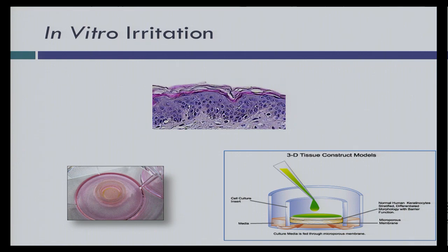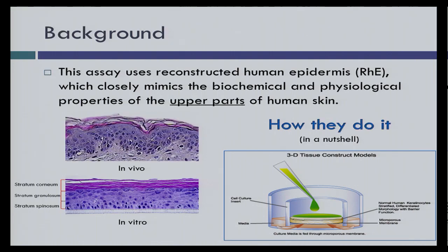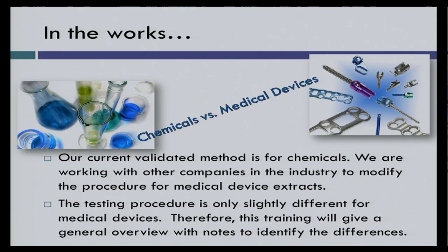The in vitro irritation alternative uses reconstructed human epidermis (RhE) — tissues derived from human skin that mimic the barrier and physiological properties of actual human skin. The current method has been validated by ECVAM (European Centre for the Validation of Alternative Methods) in a two-million-euro validation study for chemicals and cosmetics. We are now working at the ISO 10993 level to extend that validation to medical devices.